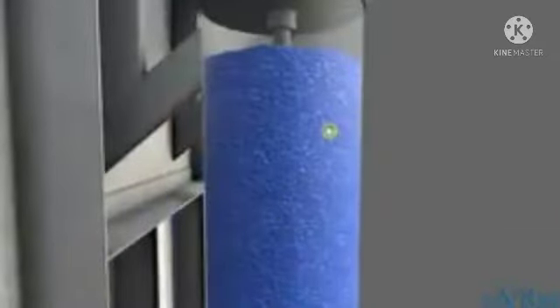There is one other interesting aspect of the silica gel breather, or the dehydrating breather, and that is the oil cup on the bottom. And this is used to separate dust particles as the air is drawn in and through the breather. So we use this oil, or the oil cup, to attract bits of dust, and as the air bubbles through the oil, we're going to separate the dust particles or foreign bodies from the airstream, and that's going to ensure that we don't get any dirt or dust going into our conservator tank and mixing with the insulating liquid. So the dehydrating breather consists of an oil cup for separating dust particles and other foreign bodies, and a silica gel breather, or a dehydrating element, which is then used to remove moisture.